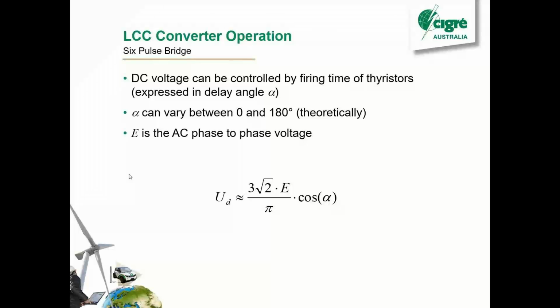Okay, I try not to put too many formulas in this presentation, but I think we have to have at least one. The DC voltage of the converter can be controlled by the firing time of the thyristors. We use a parameter called alpha, the delay angle. We can vary alpha between 0 and 180 degrees. In this formula, E is the AC phase-to-phase voltage.